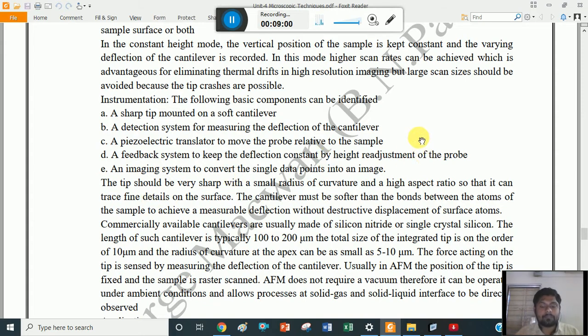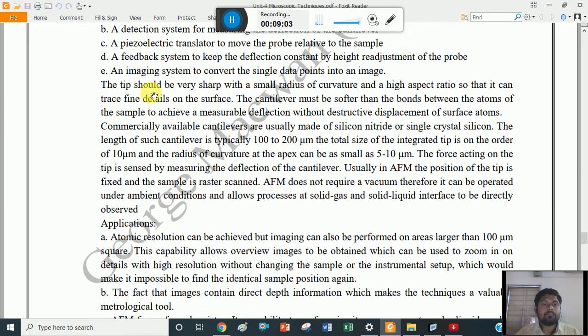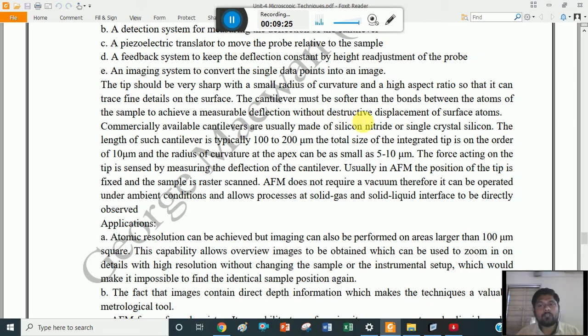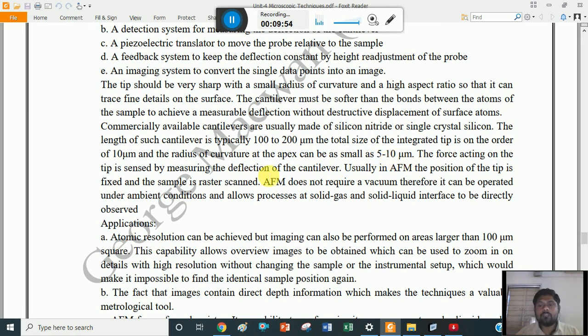The tip should be very sharp with a small radius of curvature and a high aspect ratio so that it can trace fine details on the surface. The cantilever must be softer than the bonds between the atoms of the sample to achieve a measurable deflection without destructive displacement of the surface atoms. Commercially available cantilevers are usually made of silicon nitride or single crystal silicon. The length of such a cantilever is typically 100 to 200 micrometers. The total size of the integrated tip is on the order of 10 micrometers. Radius of curvature at the apex can be as small as 5 to 10 nanometers.